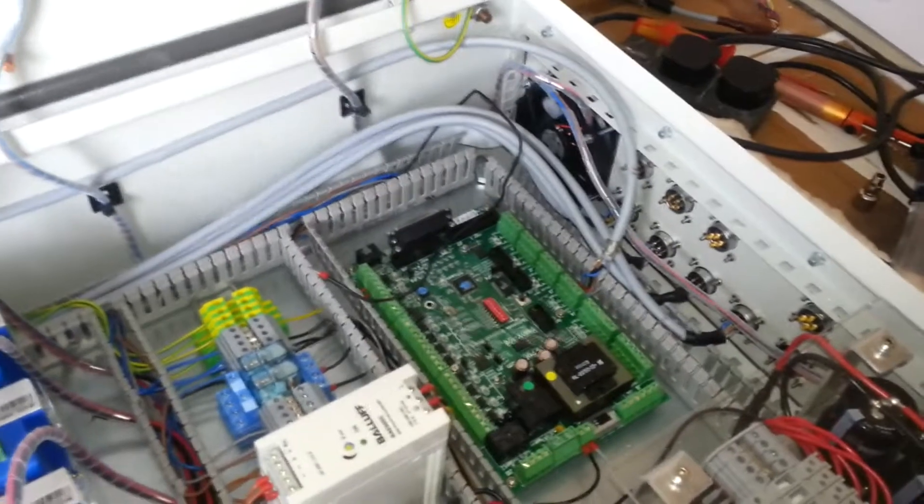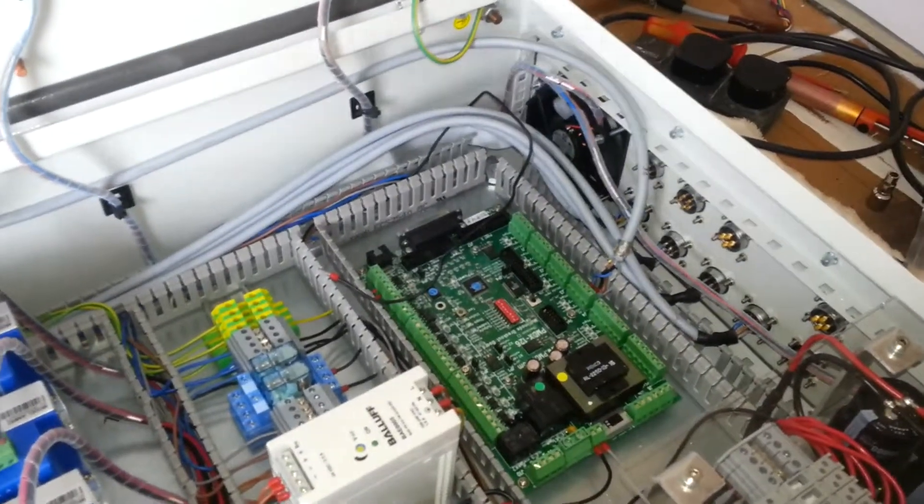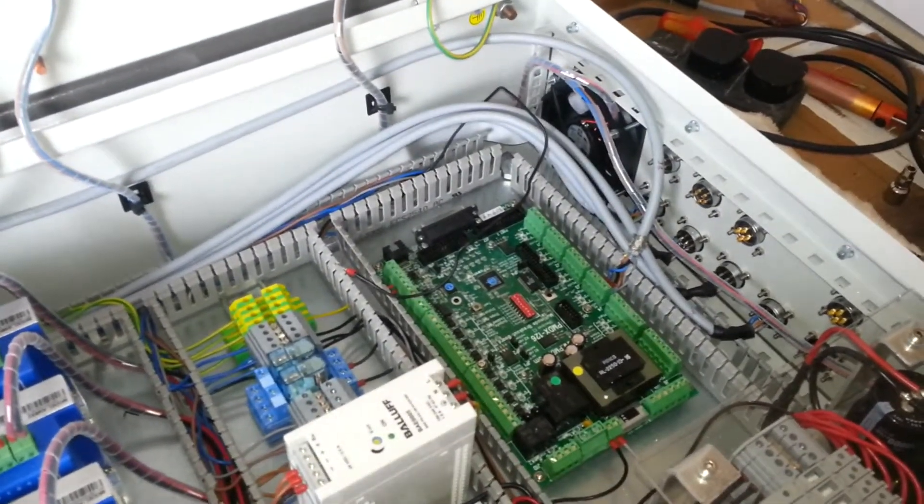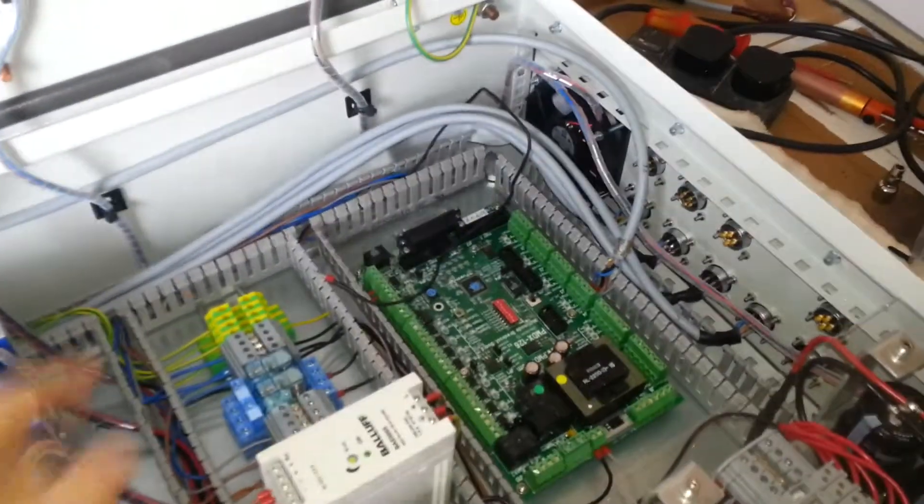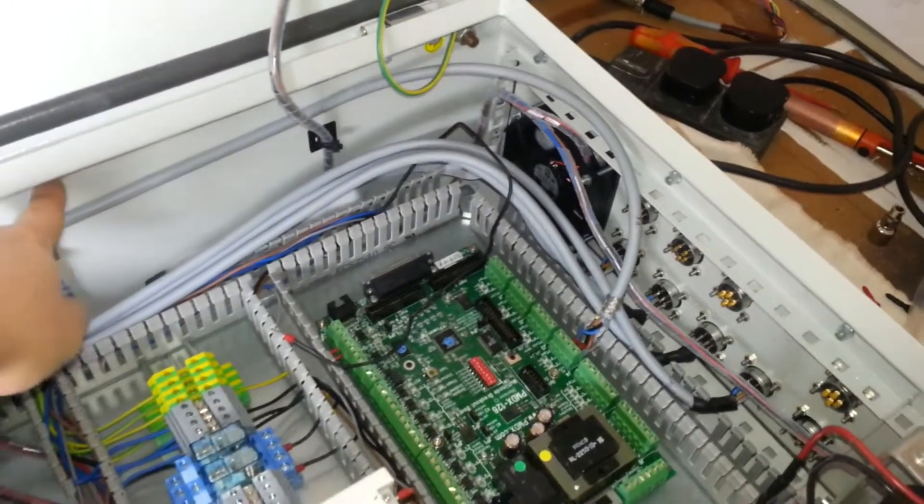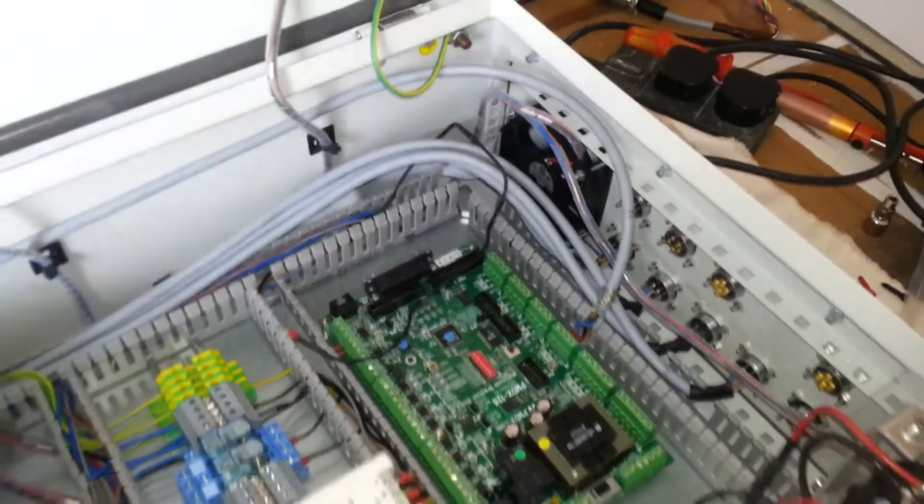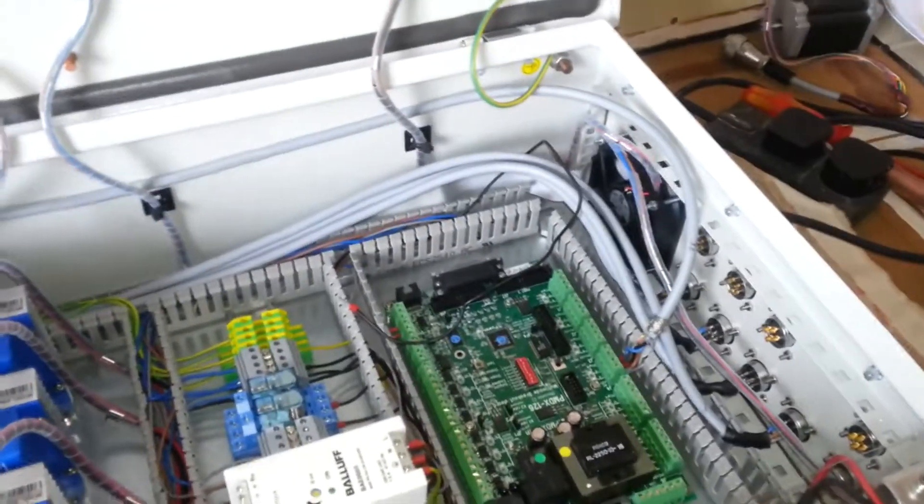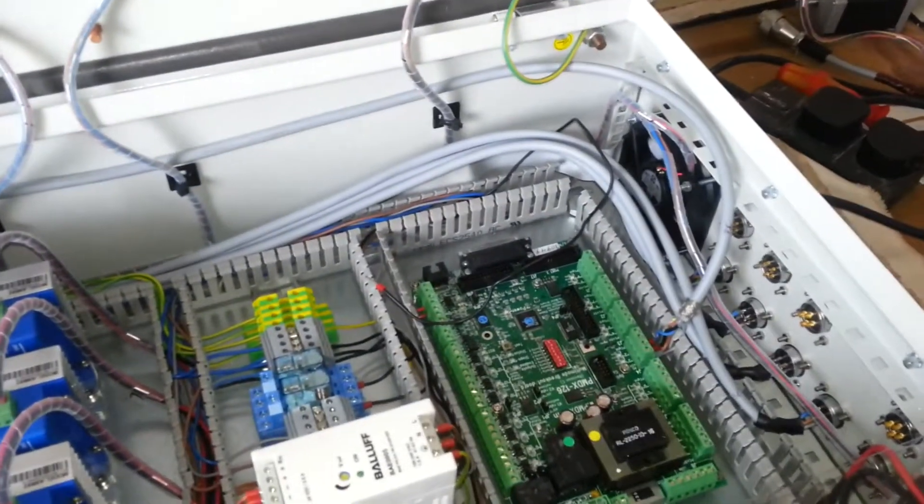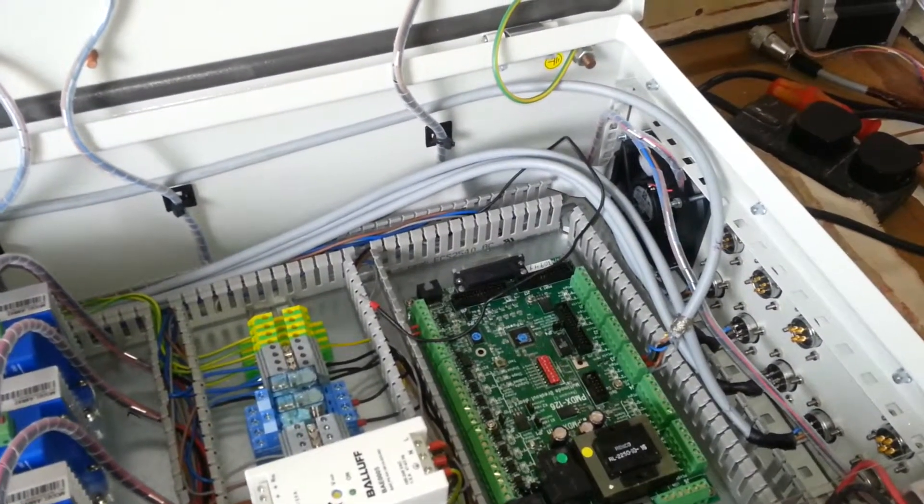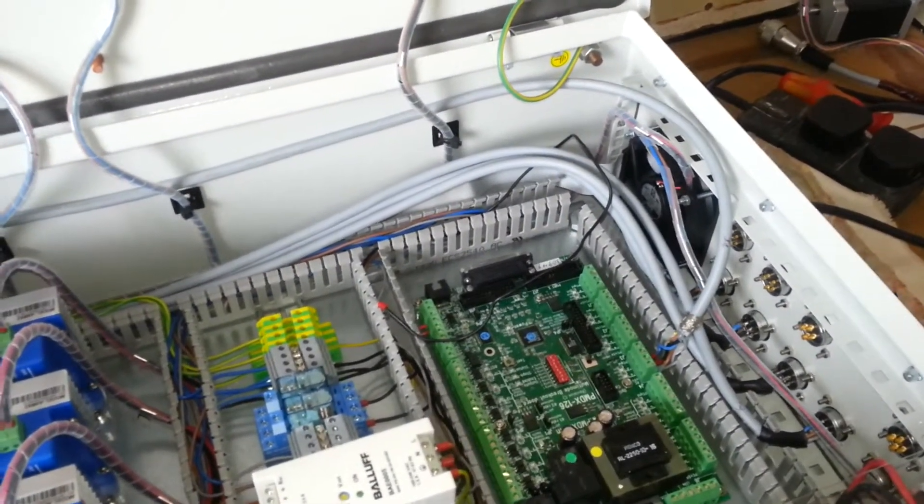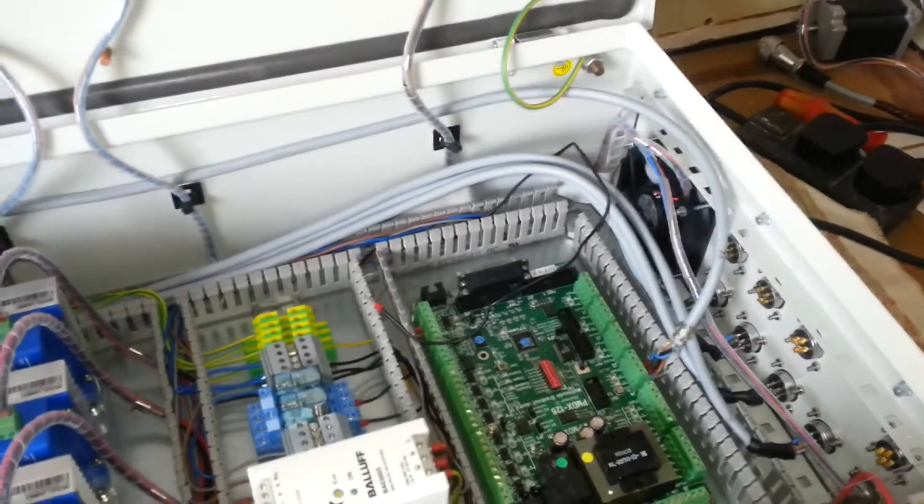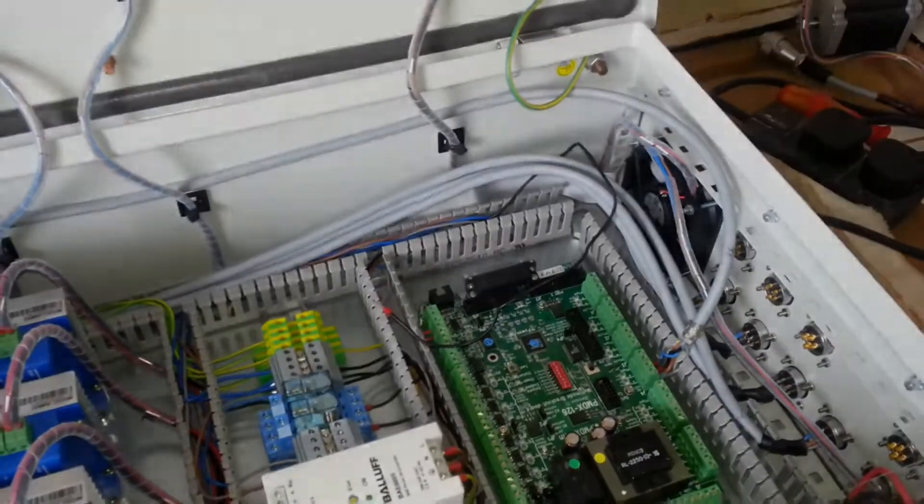yes they're shielded but it's better to keep them apart if you can. So having these run high up here, as far from, as far away from the high voltage cables as you can get, that's, yeah, less chance of interference. All around better.